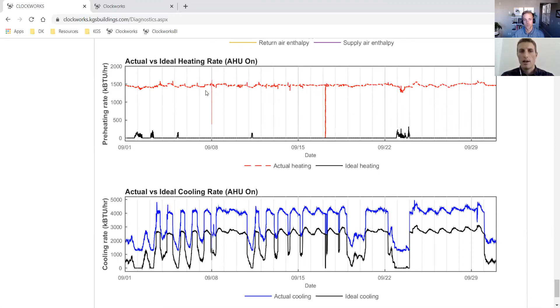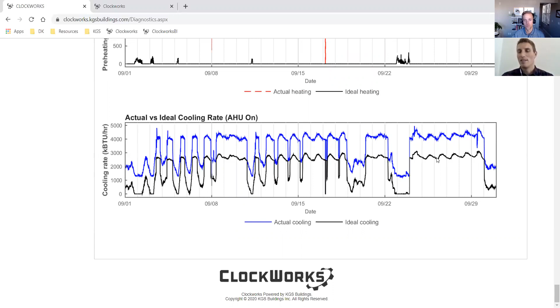And because you've heated up that air, guess what your cooling coil is doing? It's making up for it. So we're also calculating the ideal cooling rate if that heating weren't occurring in the actual, because you're leaking by. This level of modeling is what I'm talking about when I say you need a data model that understands how this air handling unit works and understands that something as simple as a preheat coil is upstream of your cooling coil.